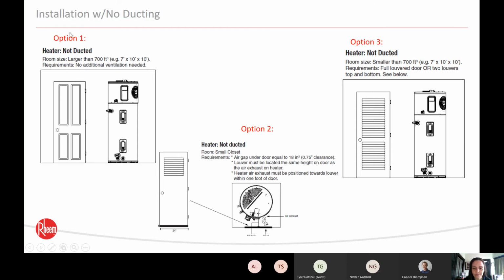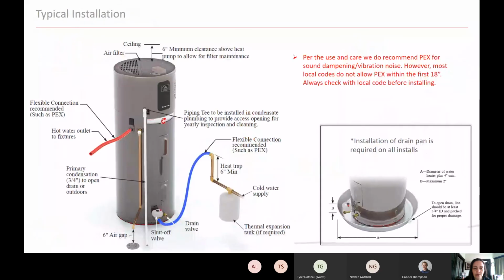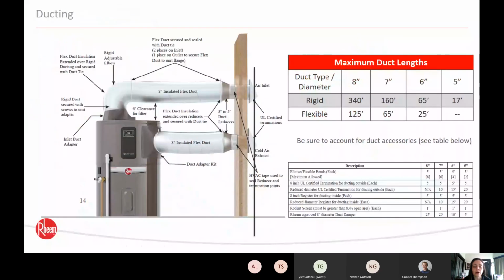So we have option 2 right here, partial louver door, 3/4 inch gap. The only thing we ask, if you look at this diagram here, remember I said that exhaust should just be kind of pointed in the general direction of your louver door. Creates a nice circulation. You have enough air volume for that heat exchange to take place. Option 3 would be a full louver door or 2 louvers at top and bottom. And that would, again, give you enough airflow for that to work. So if we don't have either of those, sorry, I put this in the wrong order. If we don't have either of those options, then we can duct.